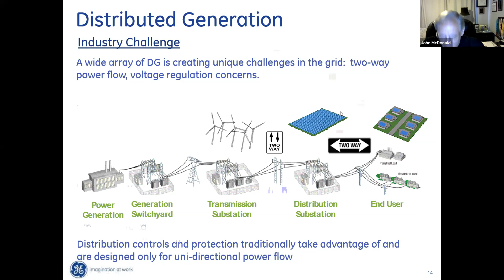Some of the challenges though, let's look at distribution. We could have open circuit over voltage due to unintentional islanding. Let's say a microgrid islands unintentionally. We could have protection ratings that don't match fault currents, right? And the reason is when we did the protection settings, the first step is you do a short circuit study. You need to know the magnitude of the fault currents to set the relays. But when we modeled the grid, we only modeled it assuming electricity flowing in one direction, and the contribution to the fault would be from the source side only. As the penetration of renewable energy grows, we could have a significant load side contribution to the fault.